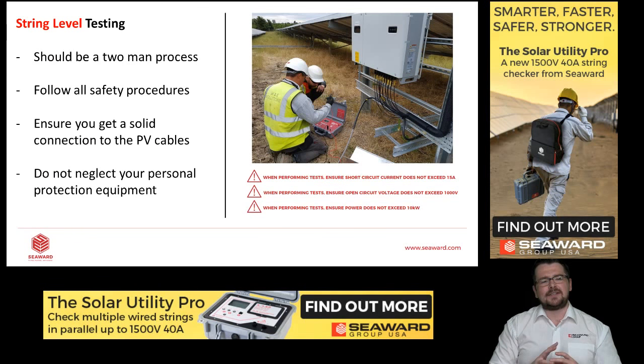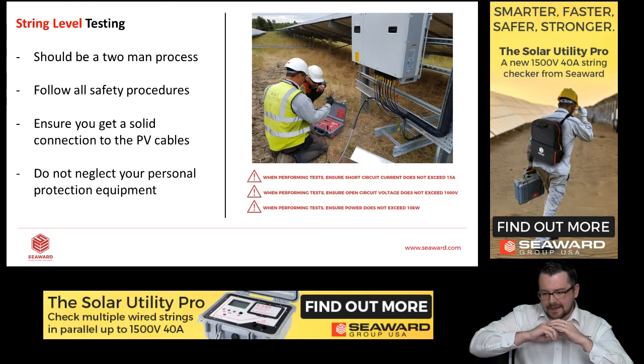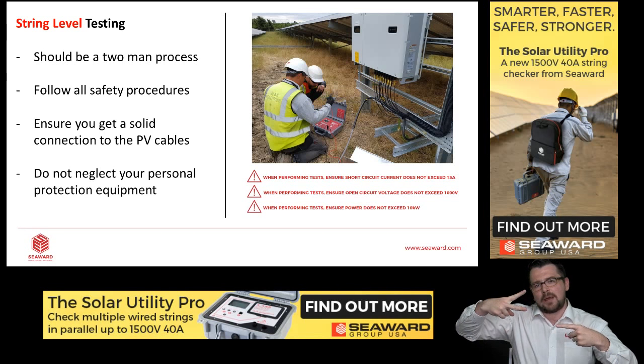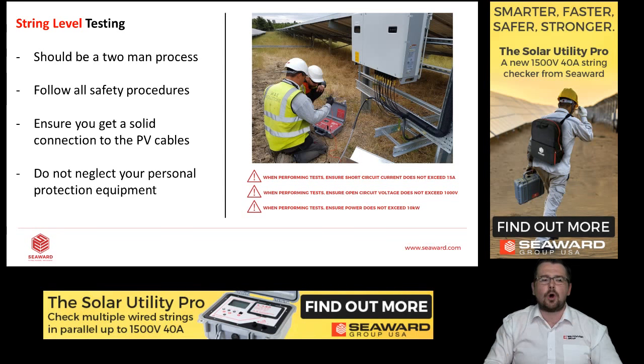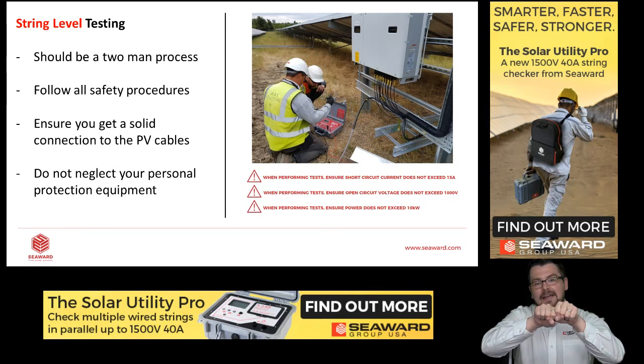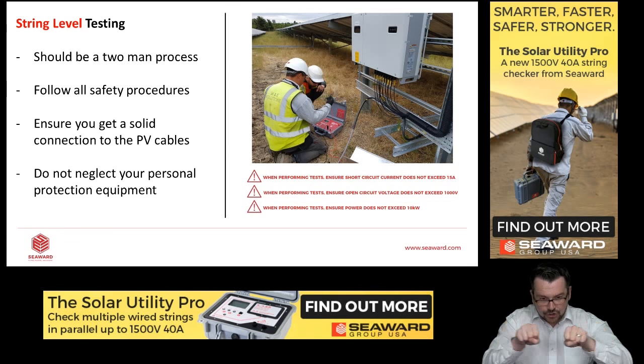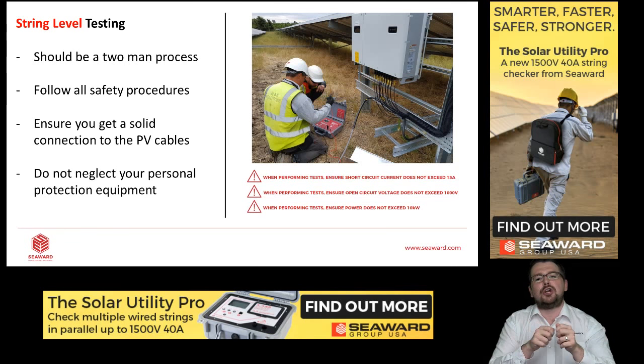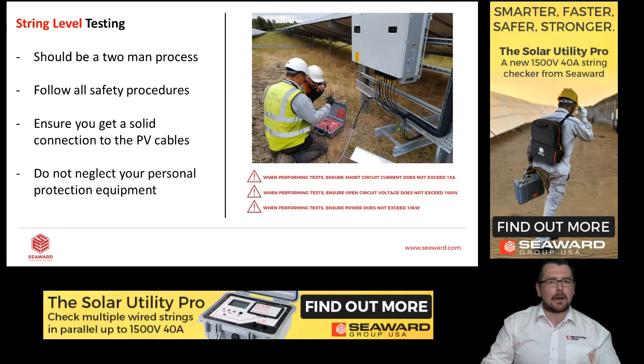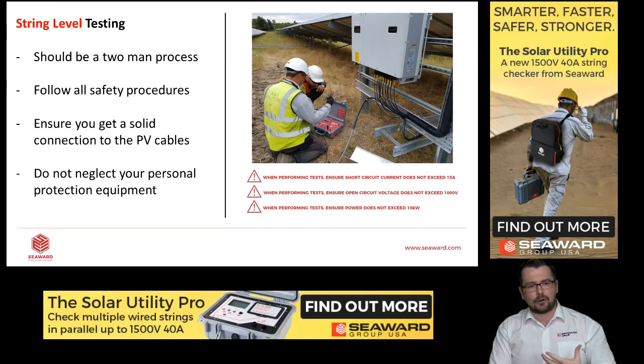String level testing is a lot easier than in a combiner box. You have a lot more confidence that you're only testing a single string, but do take a look down the string to see if you have any Y pieces which are connecting two strings into one, because that could cause an overcurrent situation. And also be careful when you're disconnecting and reconnecting the MC4s. Make sure you get a solid connection there and that there's no dirt or grit in between, or eventually that will cause arcing and insulation faults.